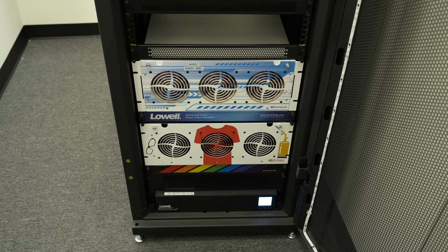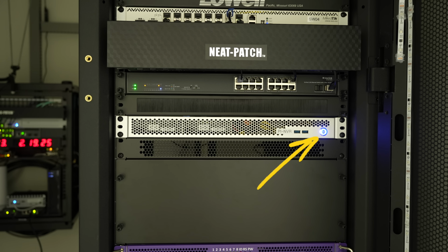That's a little weird. After a while it started beeping rapidly again, and equipment started shutting down. This is the NVR up here, it's about to shut down. Very soon after, about a 15-second delay, the Pi shuts off right after it sends a message out to the UPS to shut off. You'll see in just a moment everything else in the rack shuts down.